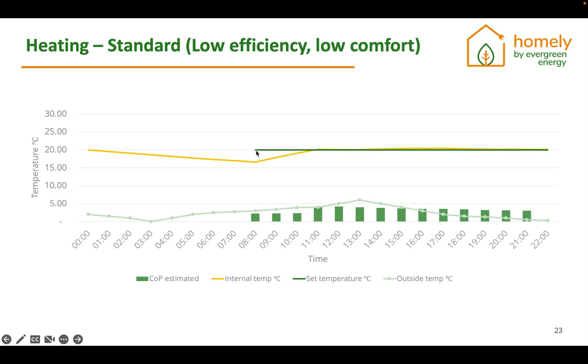So instead of the 20 degrees that they've selected, they're actually going to be at, let's say, 18 or 17. This will depend on the house and the leakiness of the house. And then it will take quite a bit of time for them to get to temperature. The low efficiency part comes in where the actual flow temperatures are going to be very high, which will mean that the heat pump is running for a shorter period of time throughout the day at very high flow temperatures, which means low efficiencies.